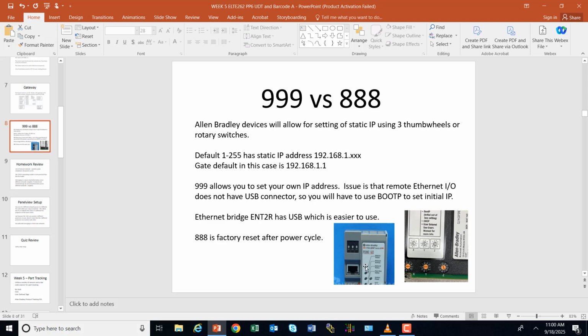Now, the problem with this remote Ethernet, it does not have the USB A to B connector. So at 999, it's going to be DHCP. You got to go into BootP, and then set up your IP that way, okay? And then you cycle it, and it will keep it as long as it's set to 999 here. You change this to a number, boom, it's going to change it back to a 192.168.1 network.